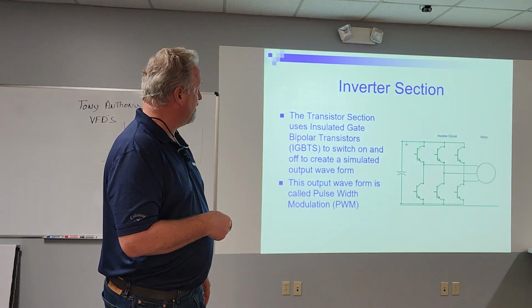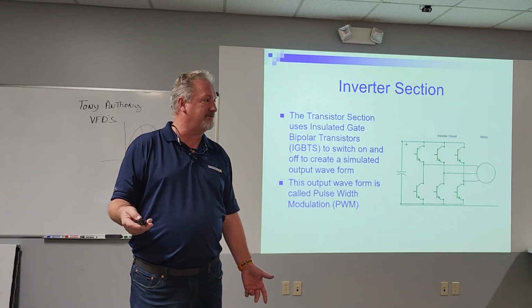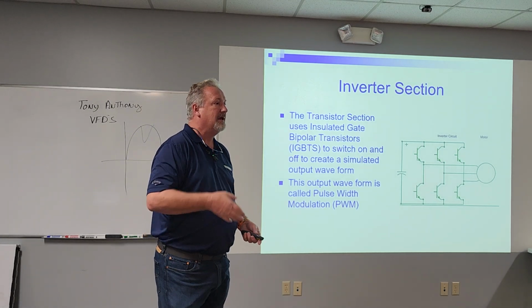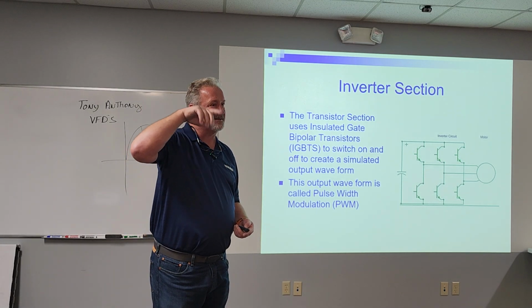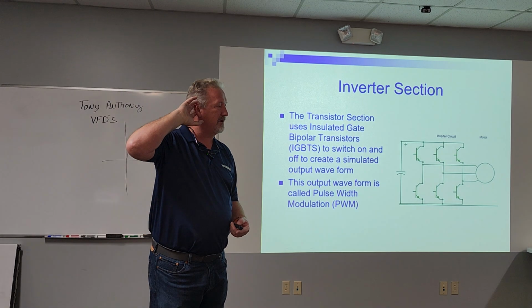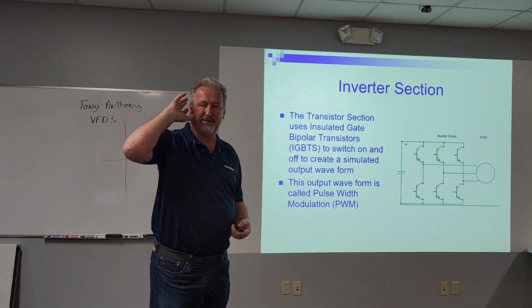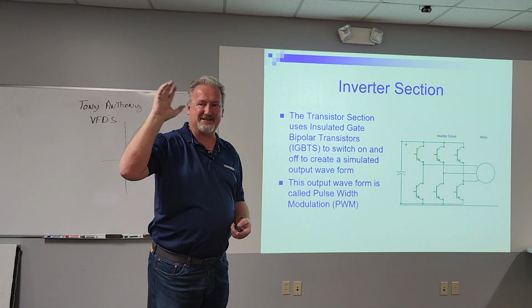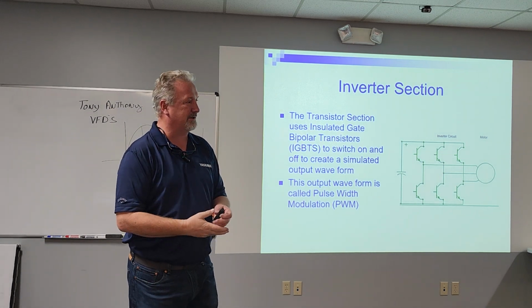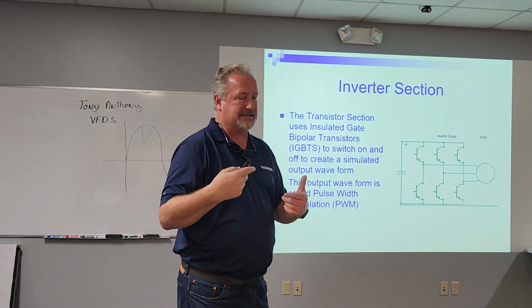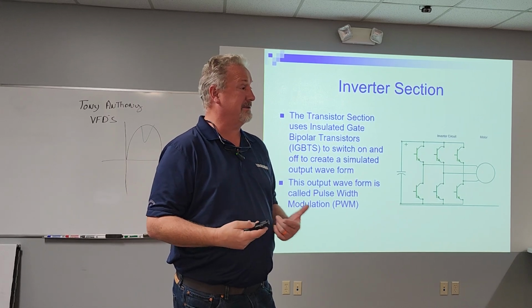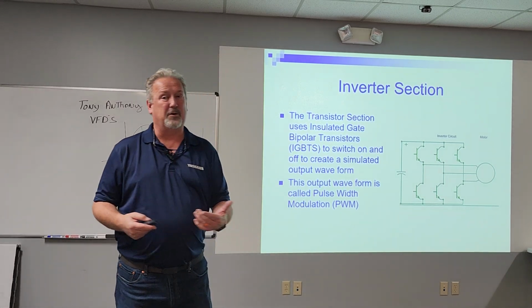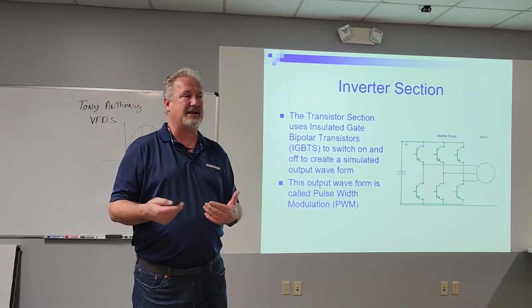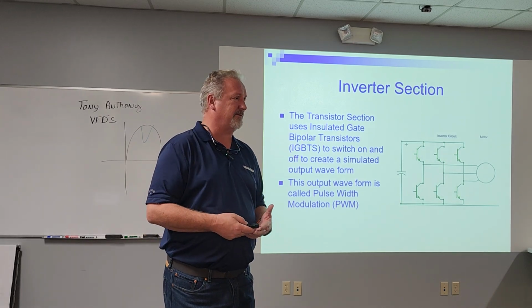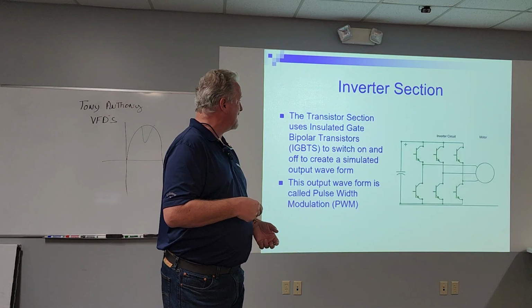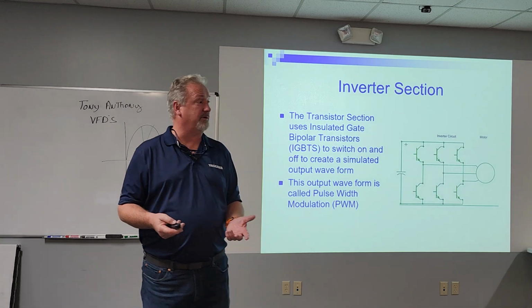It's called the carrier frequency. You've probably had to adjust that on the drive maybe at some point or another, because we're sending those pulses out to that motor. Sometimes, the motor on the drive has a whole different sound, and it kind of gets a weird sound to it because we're pulsing a DC. Well, sometimes that sound can be really annoying if it's near an office. So one of the ways you can control that, if somebody's saying, hey, this motor is really high pitched, it's driving me crazy, you can adjust how fast we're firing these IGBTs. It's called the carrier frequency.